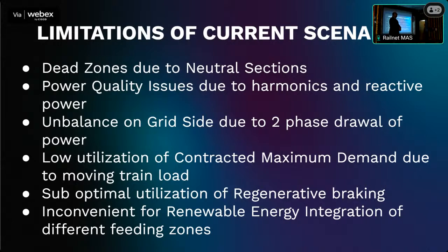Today our voltage regulation varies significantly. Whenever a Vande Bharat comes into the system, immediately when it notches up, 562 amperes are drawn, and the voltage dips immediately. At the far end of the feeding zone, the voltage dips to 19 kV. What does voltage dip mean?